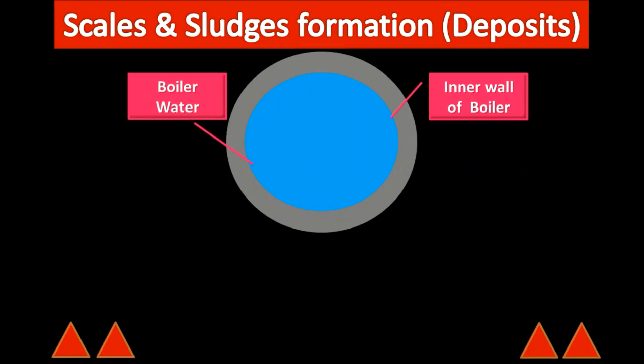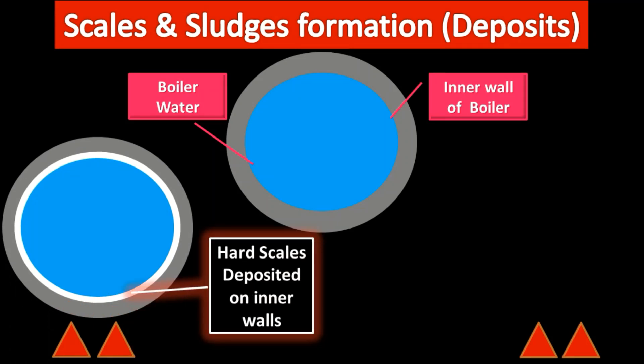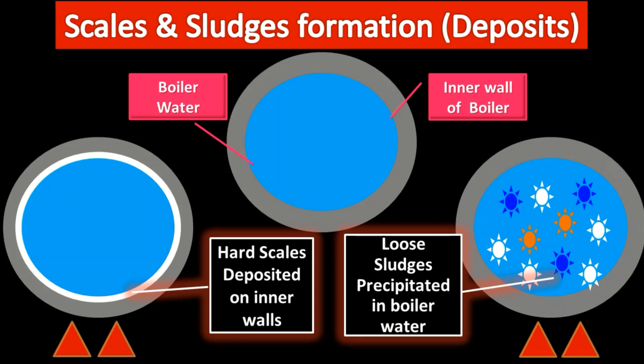Here is a better explanation of scales and sludges formation. This shows a cross-section of a boiler — the inner wall and the boiler water. We are continuously heating the boiler, and as a result the salts present get concentrated and deposited as hard scales on the inner walls. Sometimes, instead of hard scales, they can be deposited as loose sludges suspended in the boiler water. Scales are hard coatings on the inner walls, whereas sludges are loose precipitates suspended in the boiler water.